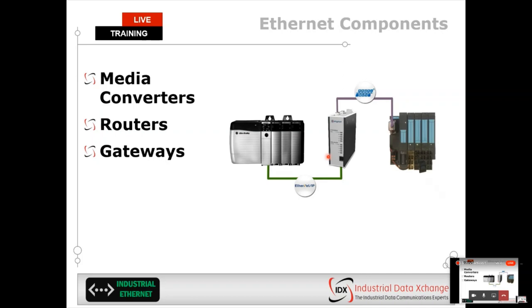Gateways: sometimes you can't connect two different protocols and expect them to talk to each other. If you have a PROFINET device and an Ethernet IP device, they speak different languages and cannot understand each other. So you need a gateway to convert between those networks. A device like an Anybus X gateway understands protocol A and protocol B and creates the translation between them, allowing information to be shared.